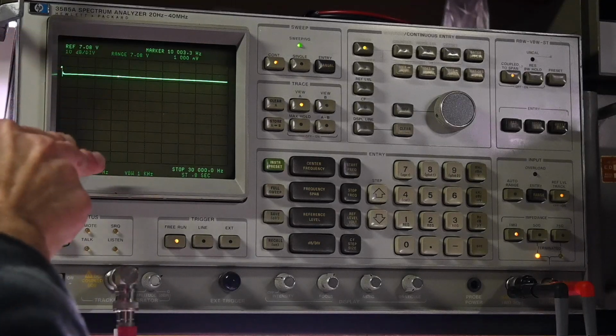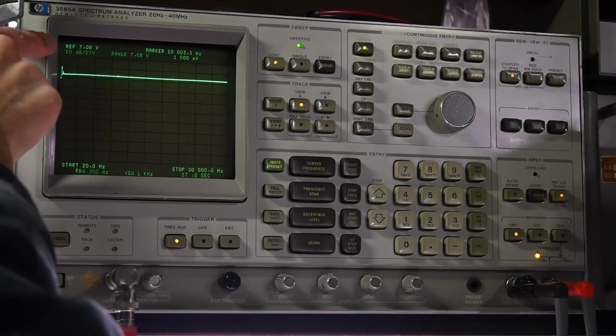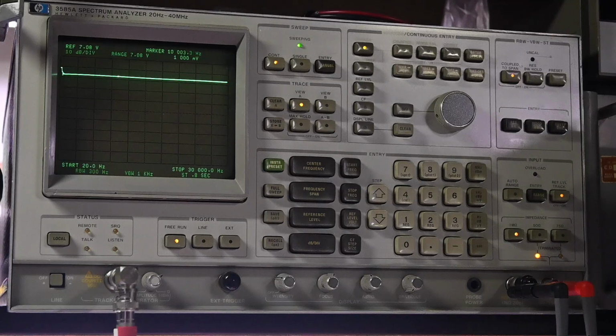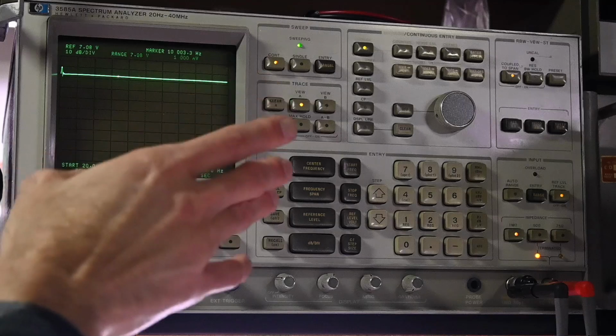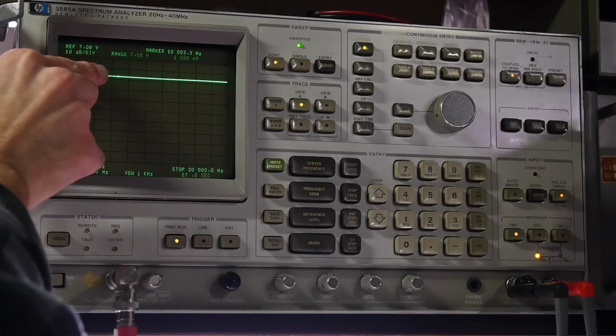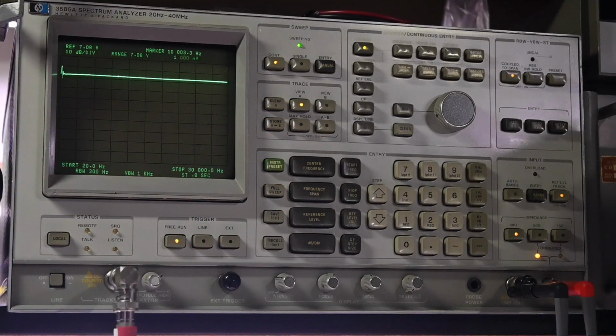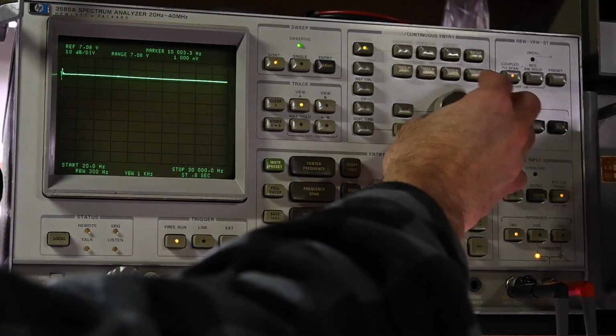Now, on the actual spectrum analyzer display, the top graticule on the very top line would represent 7.08 volts, so just a little over 7 volts. And the actual measurement, I don't know if you can see it on the camera, there's a little dot right here on the trace, and that's right at the marker, at 10 kilohertz. And this line right now is sitting at 1 volt or 1,000 millivolts, which is what it's showing up there. So that's the actual output coming out of the amplifier right now. And I do have it terminated on an 8 ohm dummy load, but anyway, that's the actual speaker output voltage right now. So you can move this marker around.